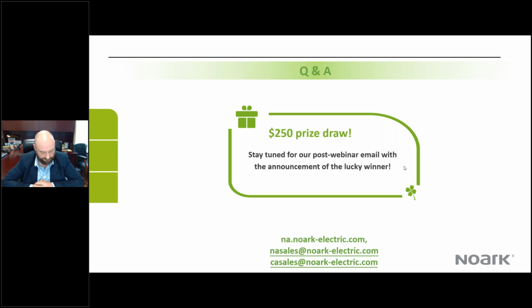Okay. Yeah, I'm not sure where you got that data from, but our 1077 is not more expensive than the UL 489. So if you look at our UL 489, they are 10 KA, they are 10,000 amps. So the KIC, the interrupting rating, is 10,000, 10 KA, while for the 1077 it's 6 KA.